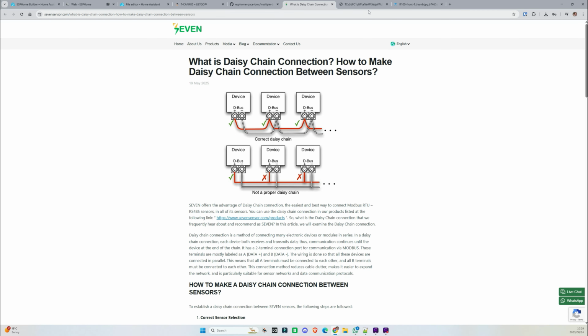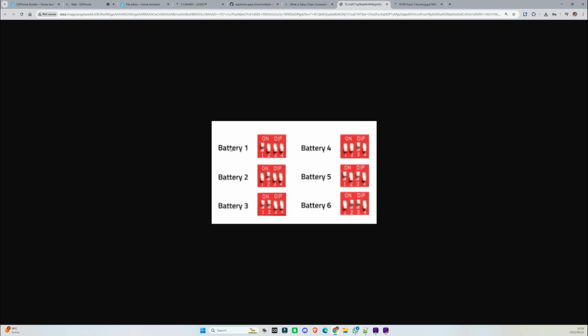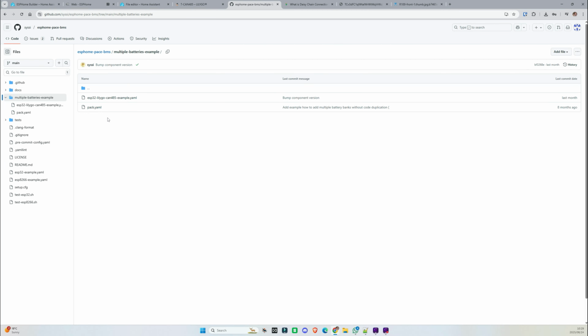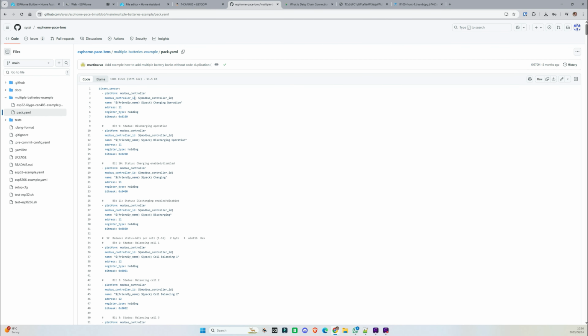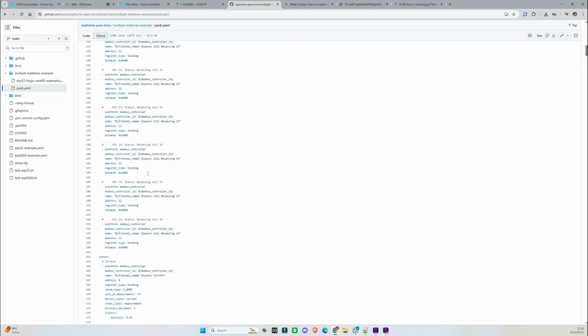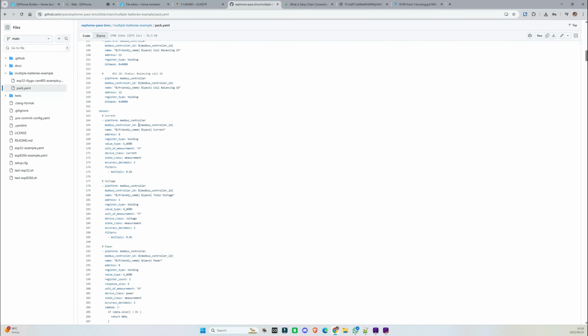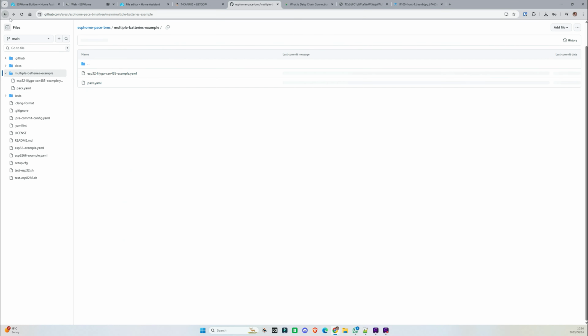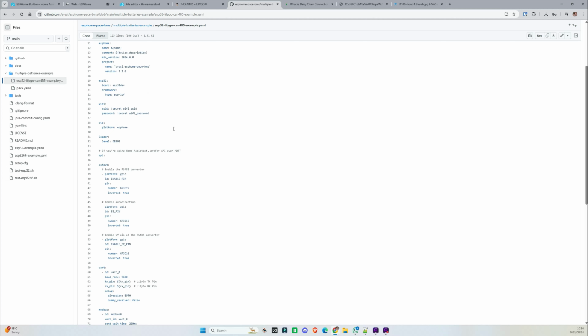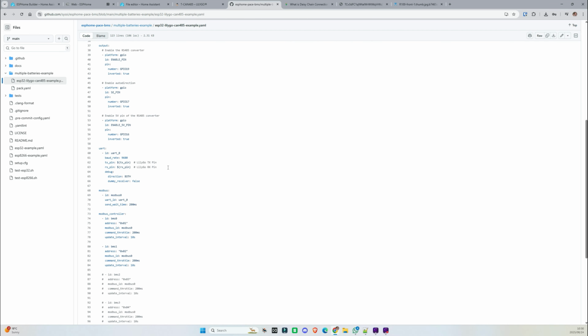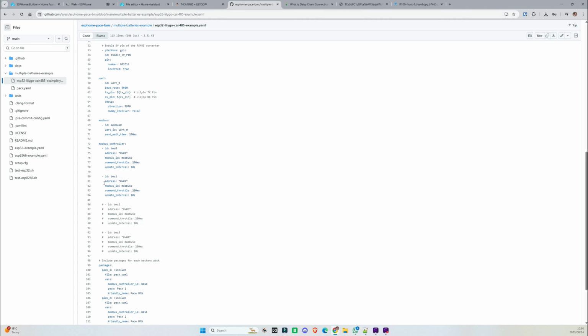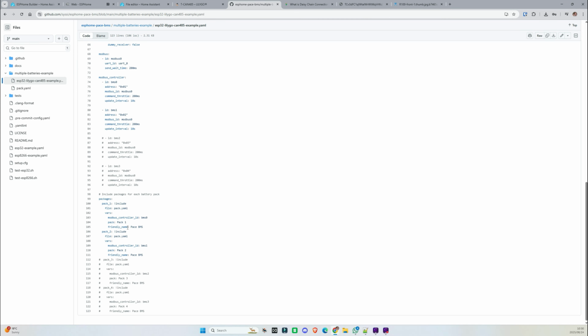Those addresses are set with the dip switches on your batteries - battery number 1, number 2, number 3 - and that is relevant to the Modbus address. So you've got your controller settings over here, where you set how many packs you have and what the Modbus address is for each pack. So there I've got 2 Modbus controllers, BMS 0 and BMS 1, and you give it the Modbus ID for each one along with the friendly name.